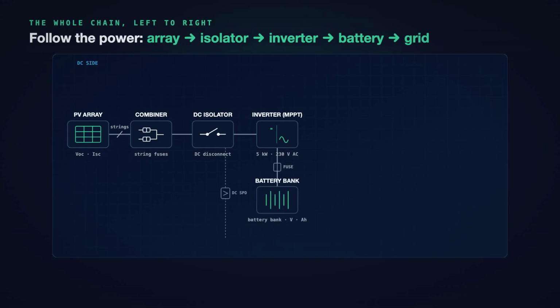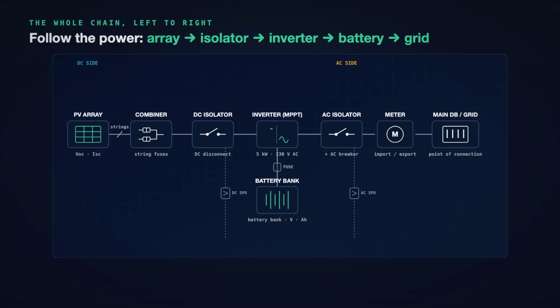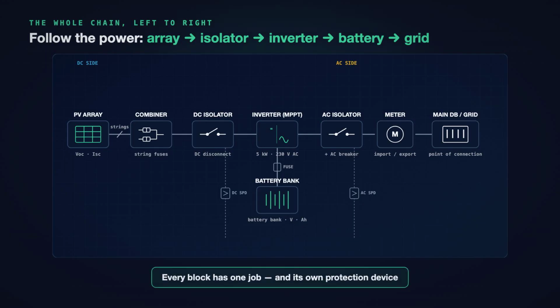If there is a battery, it hangs off the inverter through its own fuse. Then out through an AC isolator, past the meter, and into the main distribution board and the grid. Every block on that line has one job and one or two protection devices guarding it. Learn the chain, and the whole diagram opens up. Let's take it one block at a time.